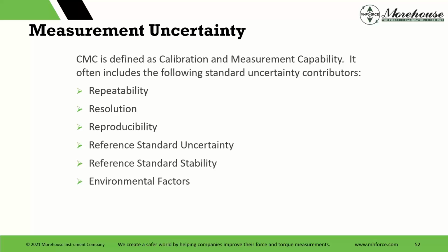So when we look at measurement uncertainty, that bias, that type B, is often not in here. You're not even going to see it in here. Look, we read A2LA R205. We read some other documents. The 5 R's and the E: repeatability, resolution, reproducibility, reference standard uncertainty, reference standard stability, and environmental factors. No mention of bias. However, I think NIST SOP 39 certainly does mention it and how to account for it and how to treat it. So you need to watch those type B errors that you could have.